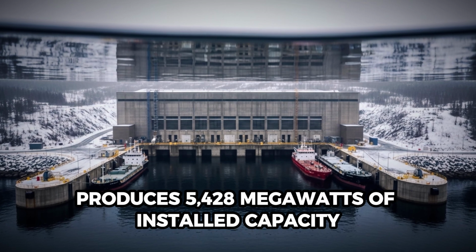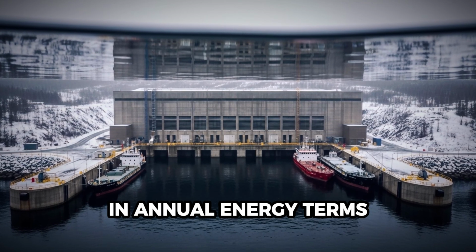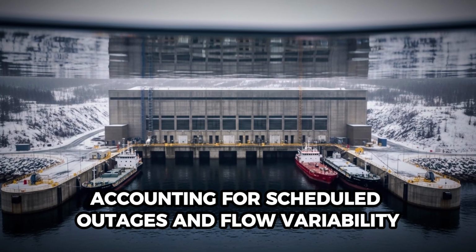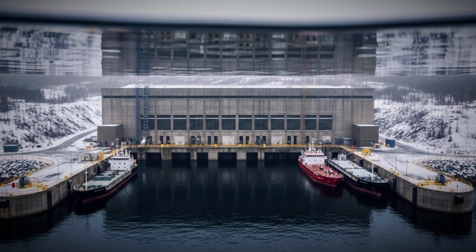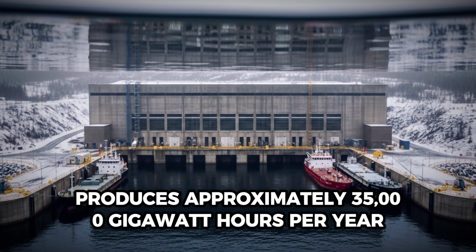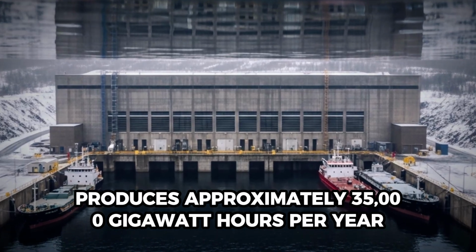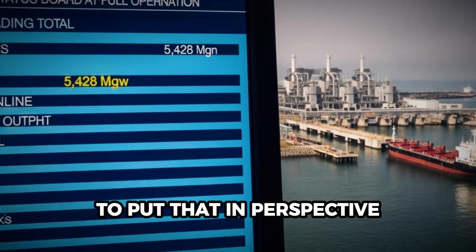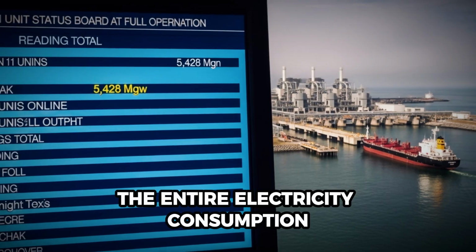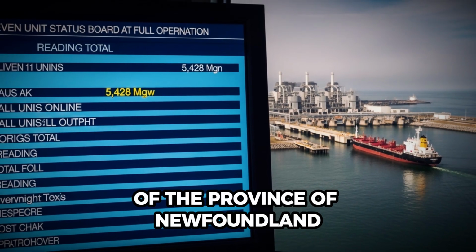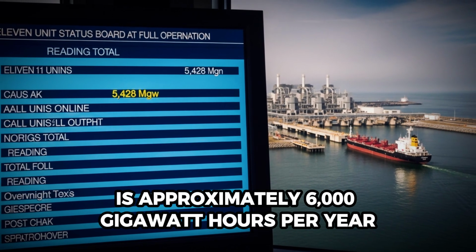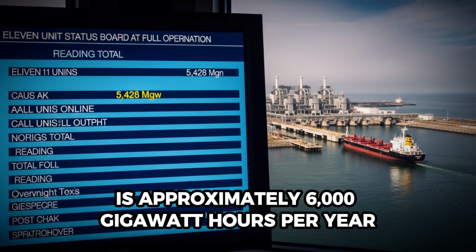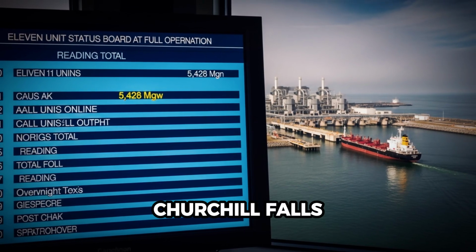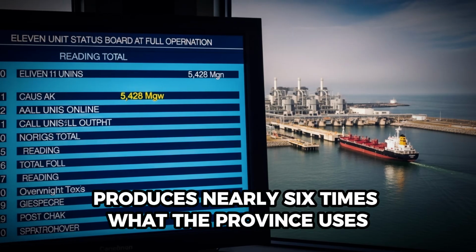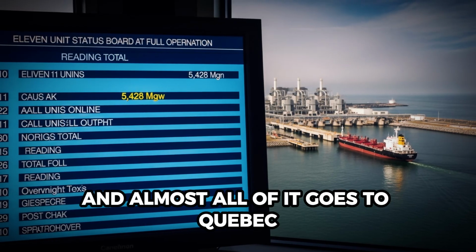Churchill Falls produces 5,428 megawatts of installed capacity. In annual energy terms, accounting for scheduled outages and flow variability, the station produces approximately 35,000 gigawatt hours per year. To put that in perspective, the entire electricity consumption of the province of Newfoundland and Labrador is approximately 6,000 gigawatt hours per year. Churchill Falls produces nearly 6 times what the province uses. Almost all of it goes to Quebec.